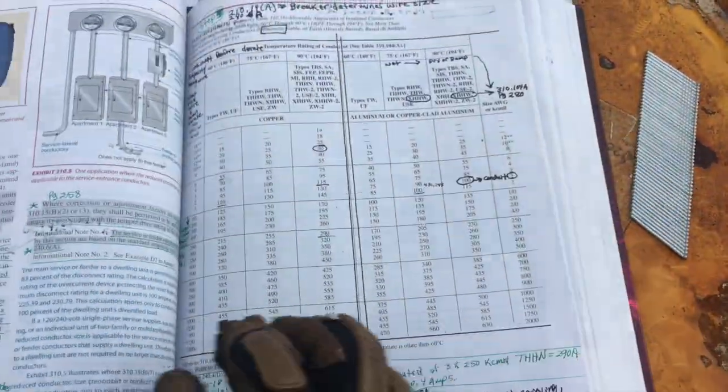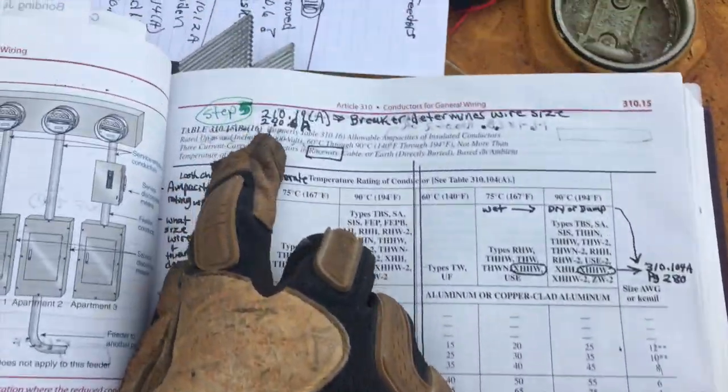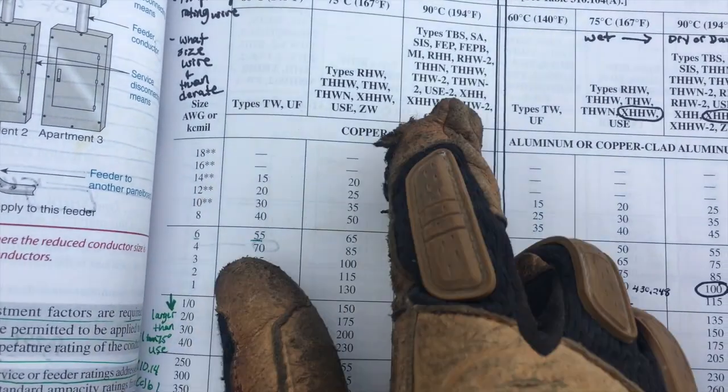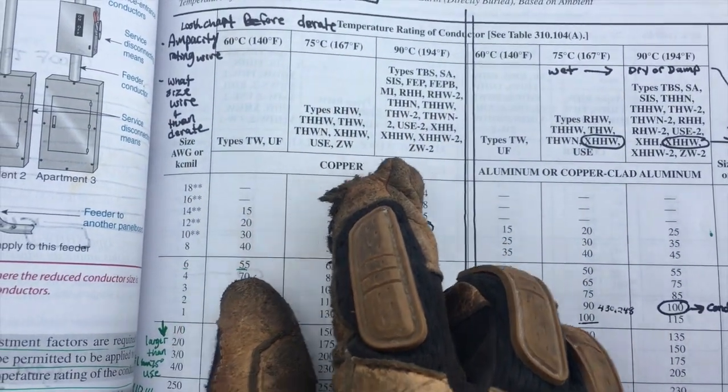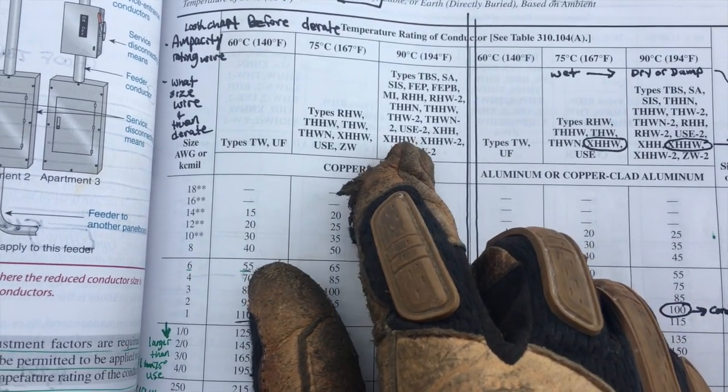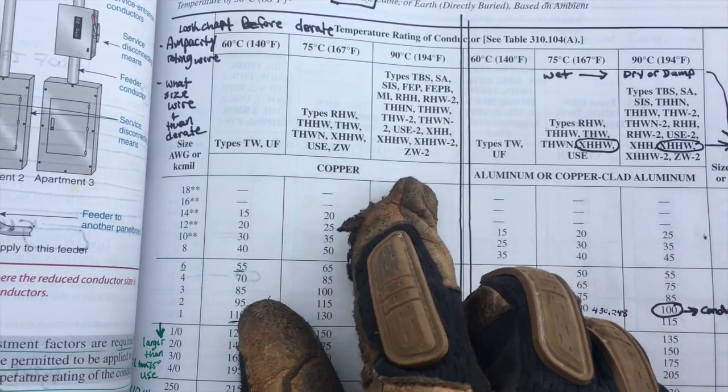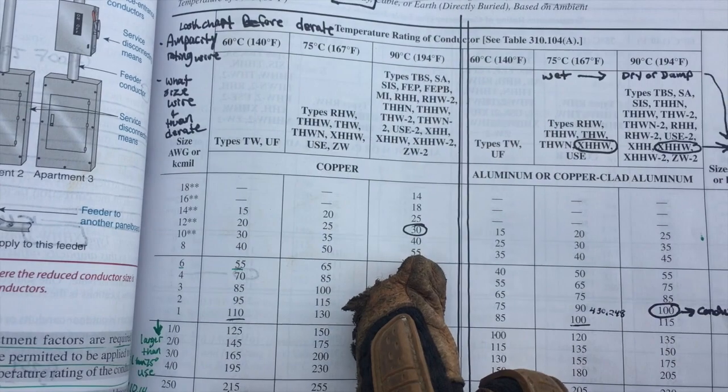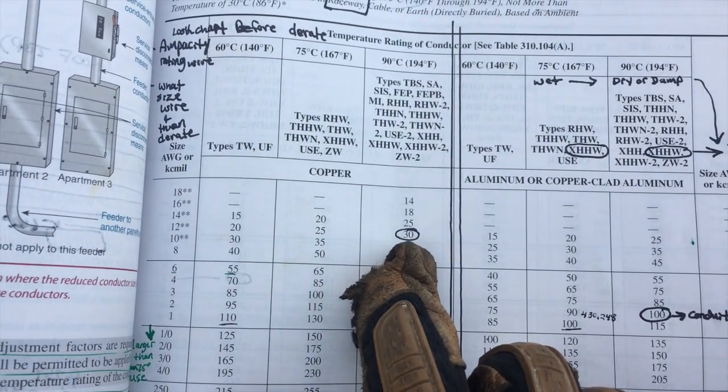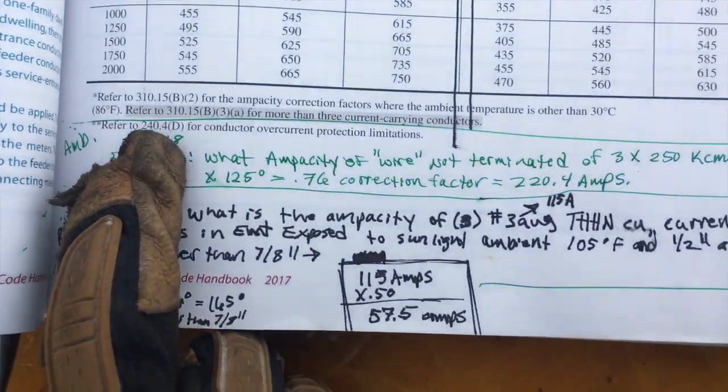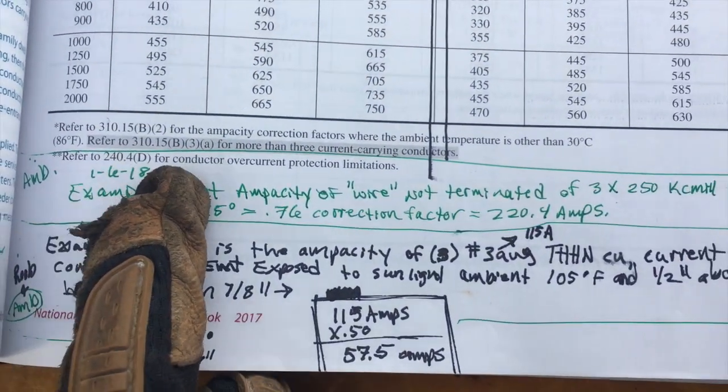You then can figure out 310.15B16, that a number 12 gauge copper THWN-2, that's all I ever buy, rating is 90 degrees Celsius column, and that is good to 30 amps. Pay attention to the asterisk mark which drops you back down here to say pay attention to 240.4D, your conductors over current protection limitations for anything smaller than a 10 gauge.